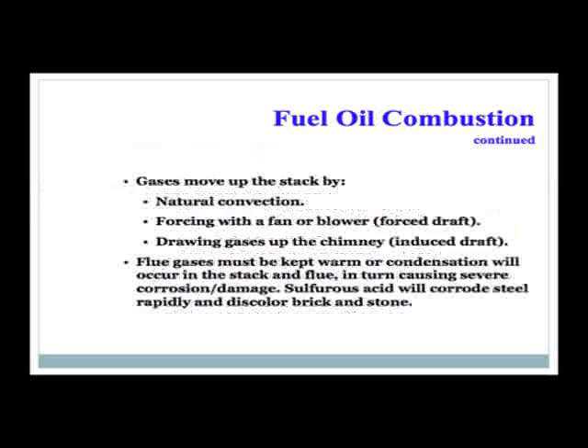Gases move up the stack by natural convection. Some are forced with a fan or blower — this is called forced draft — and some are drawn up the chimney with induced draft. Flue gases must be kept warm, or condensation will occur in the stack and flue, causing severe corrosion and damage.